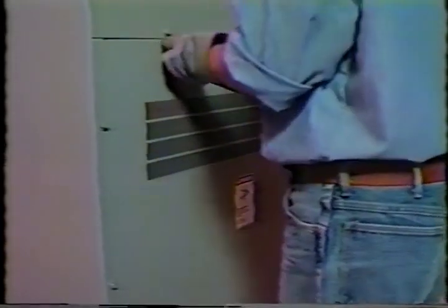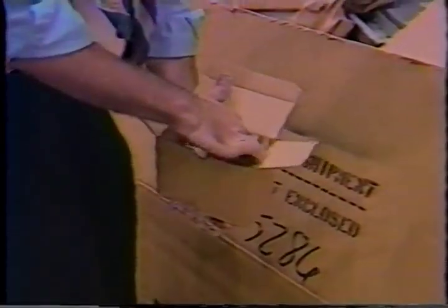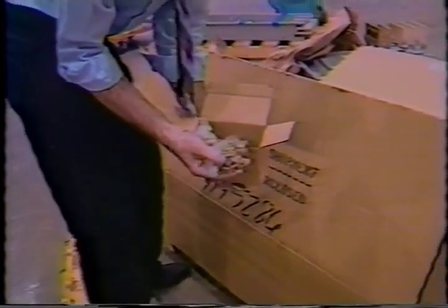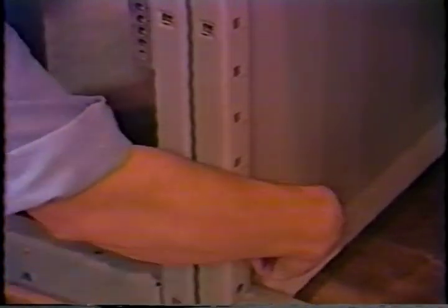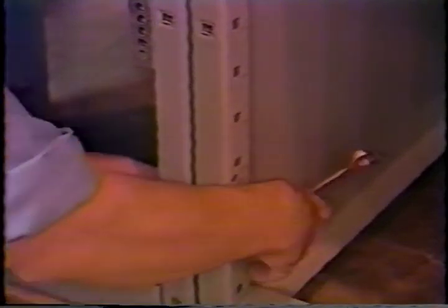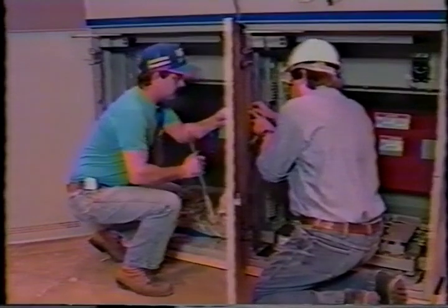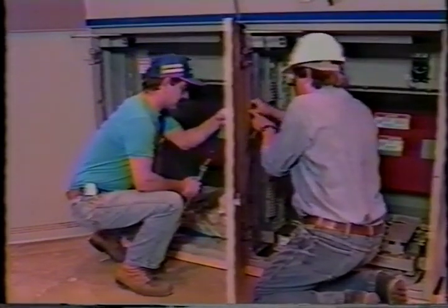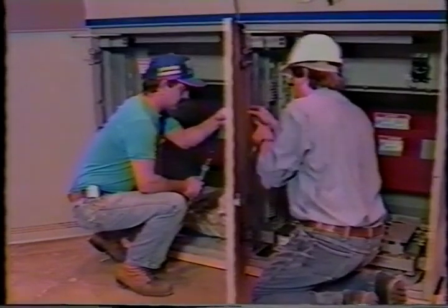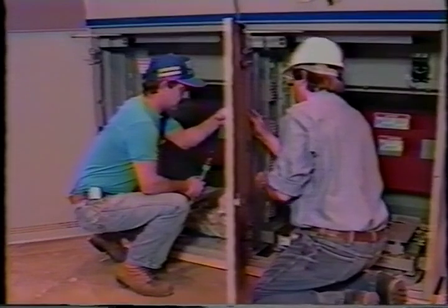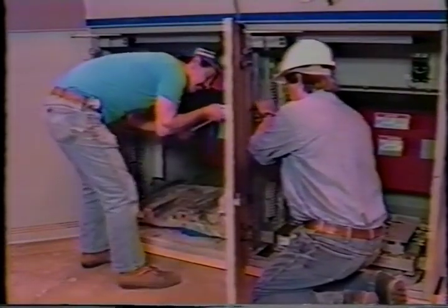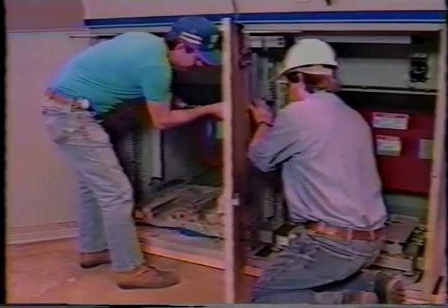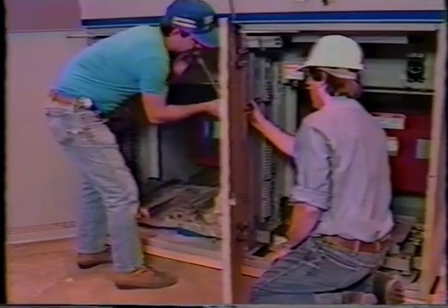Remove the back cover from the vertical section at the shipping split. Remove the tie bolts from the cardboard detail box. Insert and tighten tie bolts in the rear upright members. Open the front panels on these vertical sections. Insert and tighten tie bolts between the front upright members. Bolt or weld the entire switchgear system to the channels in the foundation. Remove all shipping blocks or braces.